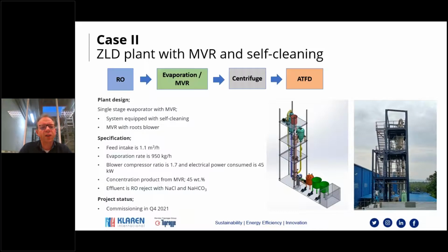In this case, we talk about a ZLD plant, meaning that the plant aims to provide only solid waste and make a maximum recovery of the water content, which is, in terms of water scarcity, of course, very beneficial. The client already had an RO plant installed, which is a very good thing, because in terms of energy efficiency, it's good to use membranes as a first step of concentration. But membranes have their limit, and I think 80% of the volume is already recovered by then. For the last 20%, if you want to come to ZLD, evaporation is a good choice.